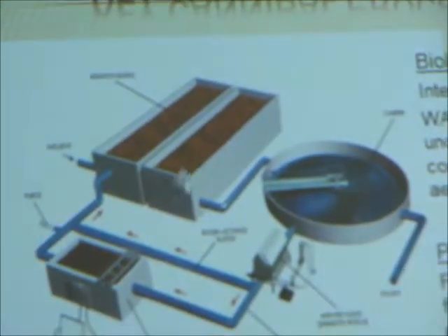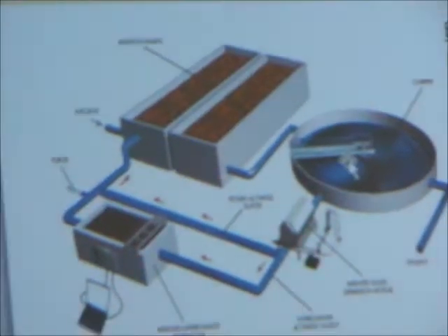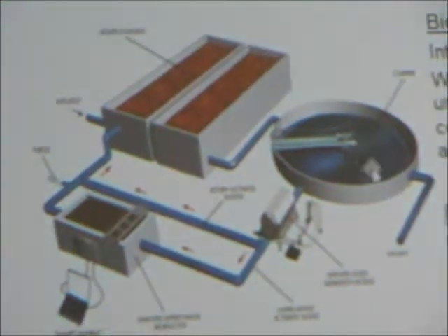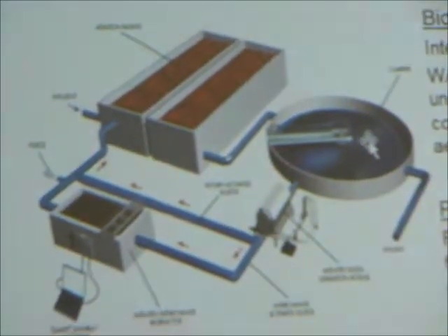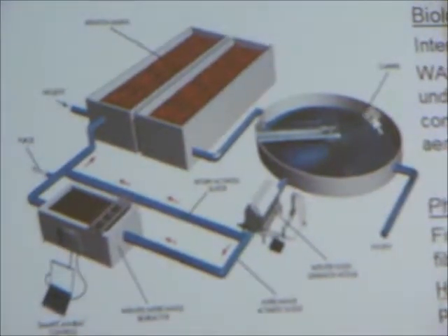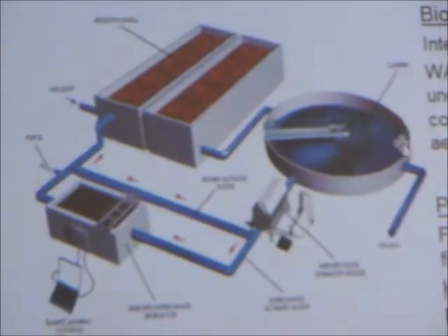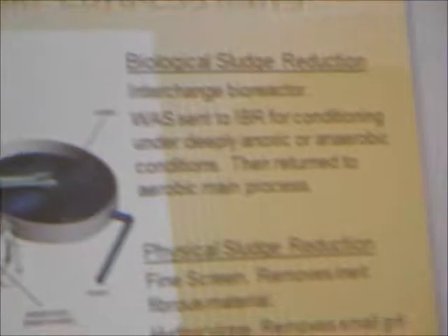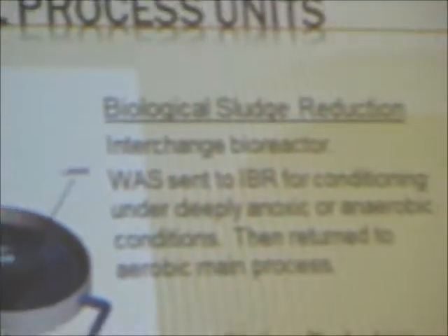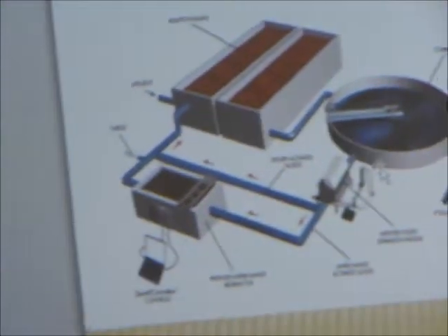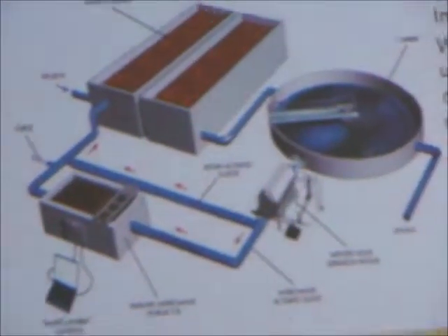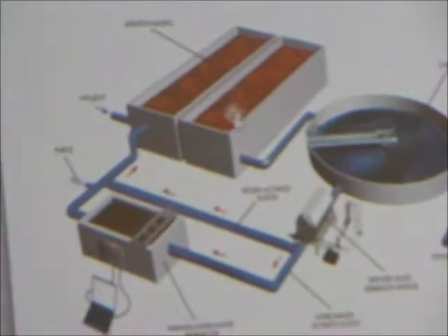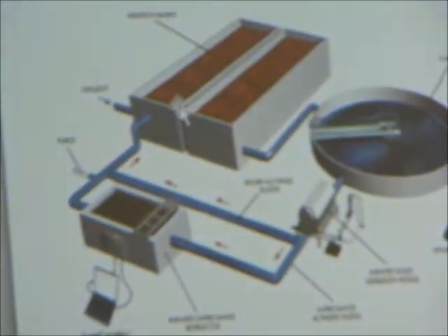So at the end here, you transfer your mixed liquor into your secondary clarifier, and in this secondary clarifier you have your solids-liquid separation. This is where you produce your clarified effluent, goes over your effluent weirs, and then after disinfection, you're at the final stage of the treatment process. On the sludge side of that, the solid side of that, you're drawing your RAS, your return activated sludge, off the bottom of this clarifier, and that will go back to your process to consume what influent you have coming in.